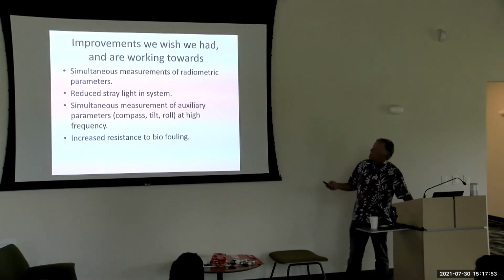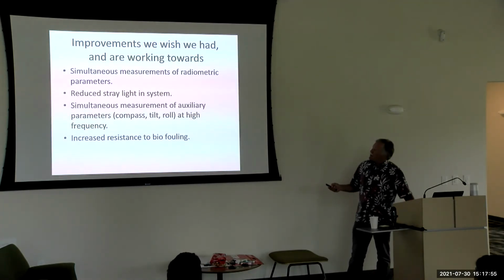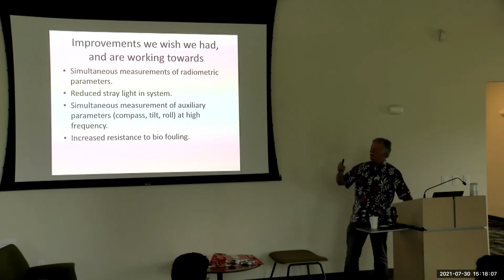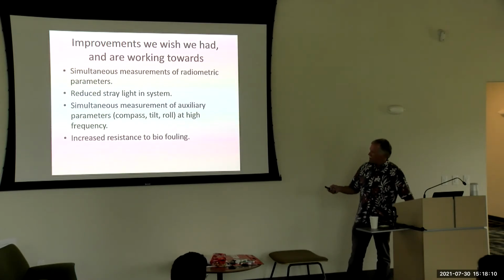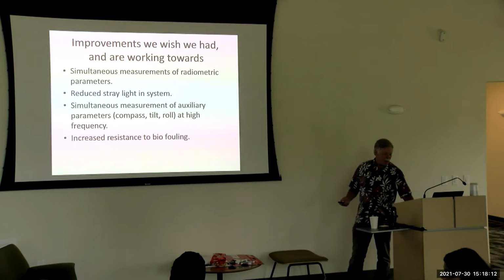Things we wish we had and are working on are simultaneous measurements, and reducing stray light in the system, because that's an error term. We want better measurements of the compass, tilt and roll, so we have a better idea of the orientation of the instrument. It would also be nice to reduce biofouling.